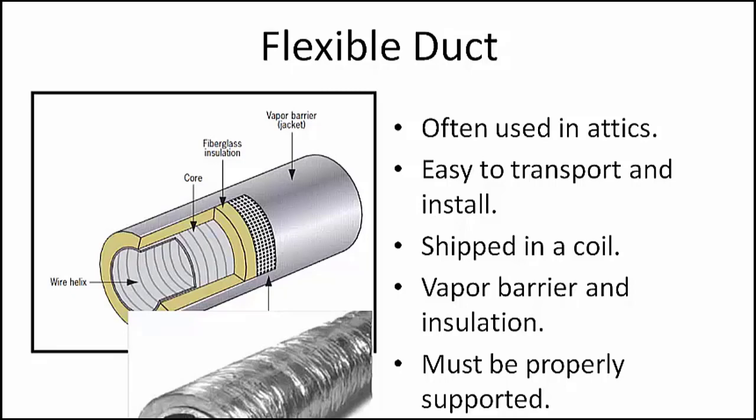Flex duct typically is shipped in a coil of 25 feet to the box. It consists of a metal coil and insulation, often with a vinyl or foil outer coating as shown in this slide. Flex duct must always be stretched tight and supported properly to ensure proper airflow through the duct. Excessively long or sagging runs of flex duct will restrict the airflow and create problems in the system and in the conditioned space.